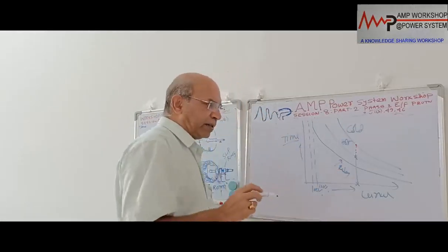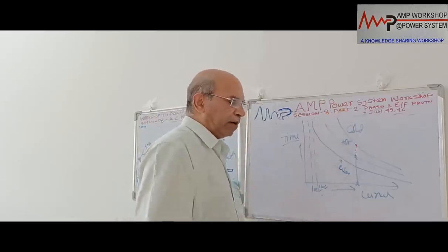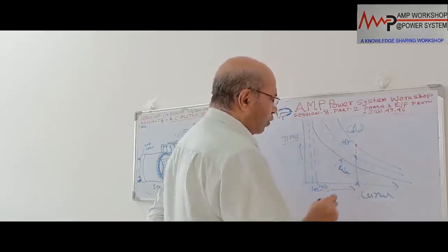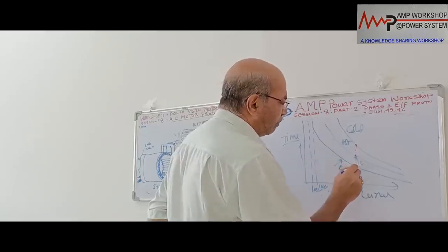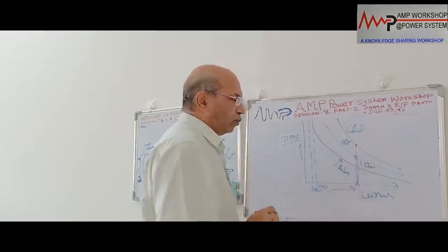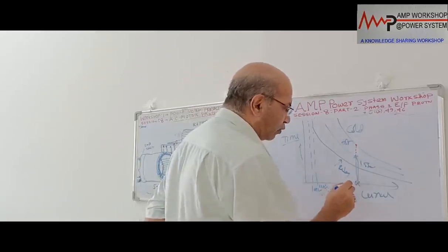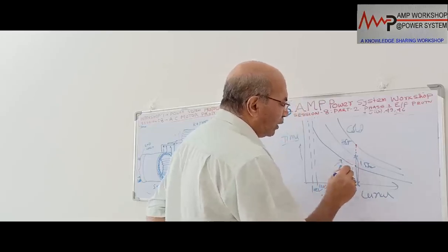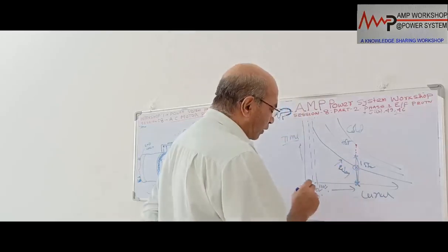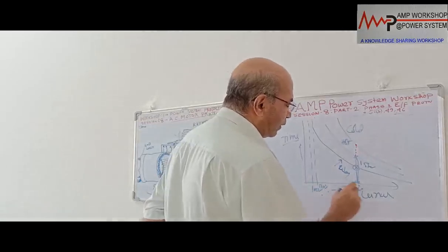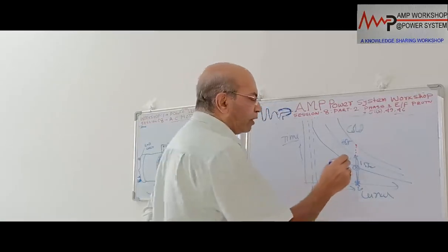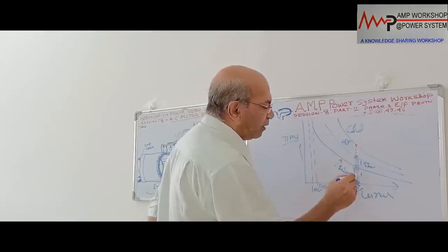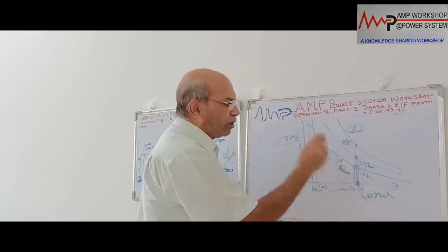So the protection device curve will always lie below the motor curve. Suppose the motor is running, and at this condition the motor withstand time is 15 seconds. If the current comes to this value, the motor should trip immediately, before this. So this is the tripping time of the motor. Suppose the current magnitude is 200%. The motor can withstand 200% current for 15 seconds, so I have to trip the motor before that. Here the tripping time may be 10 seconds, so it will trip immediately.